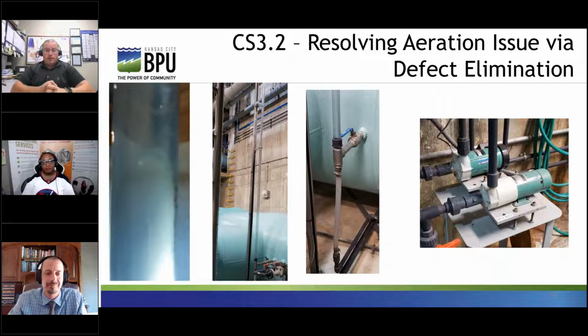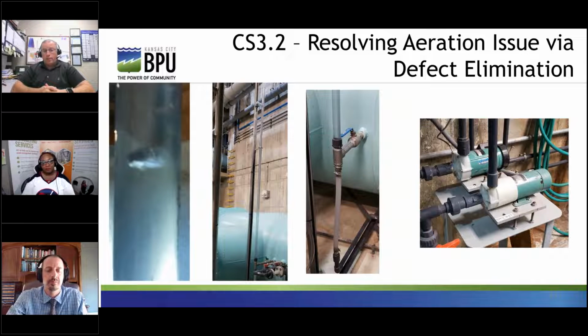Image 2 is of the complete finished solution, a large clear PVC weir. The third image is a close-up of the sample point and lets you see the simplicity of the design: a straight nipple T, clear Schedule 80 PVC pipe going up to release air, clear PVC tube feeding the pump of water free of air. The fourth image is the result of replacing the turbine regenerative pumps with magnetically coupled pumps of a much more appropriate size.